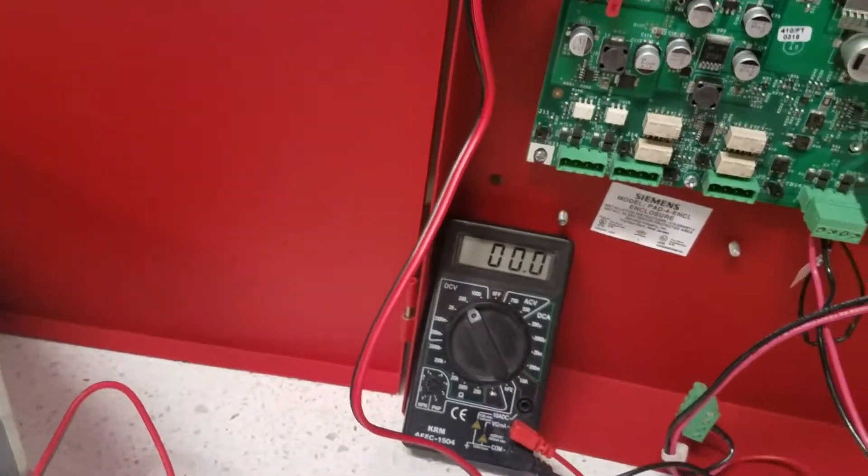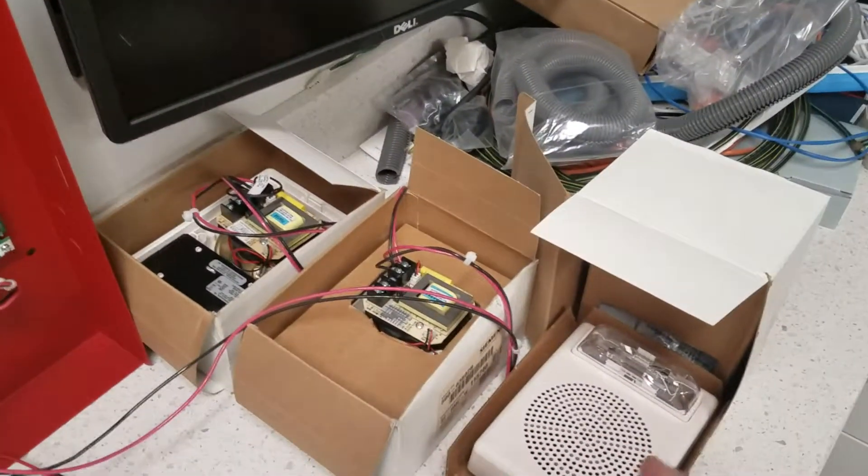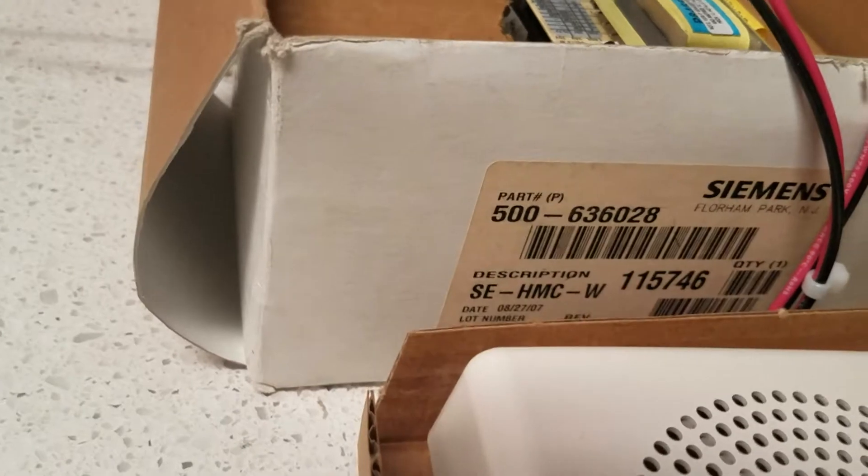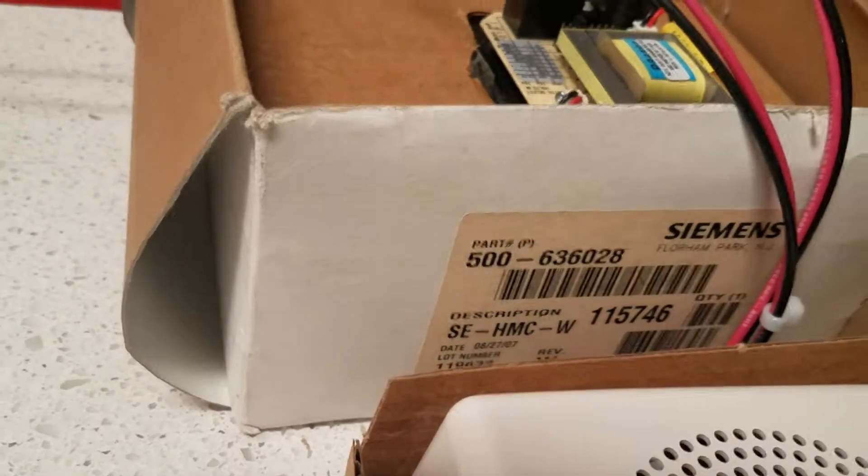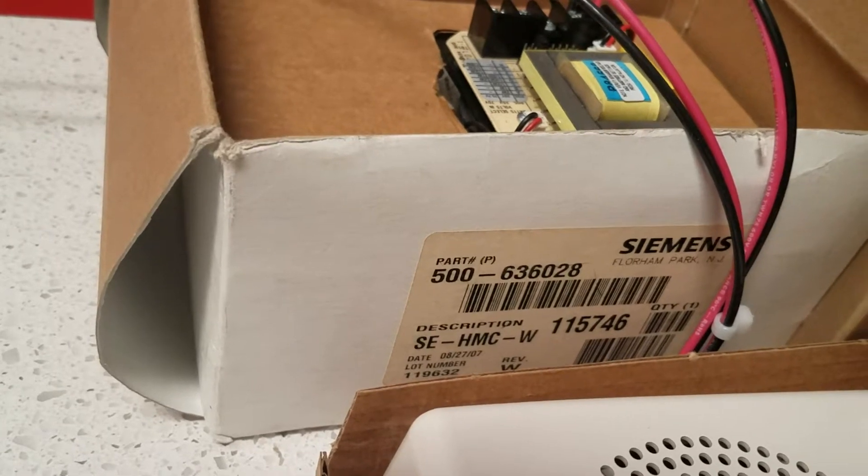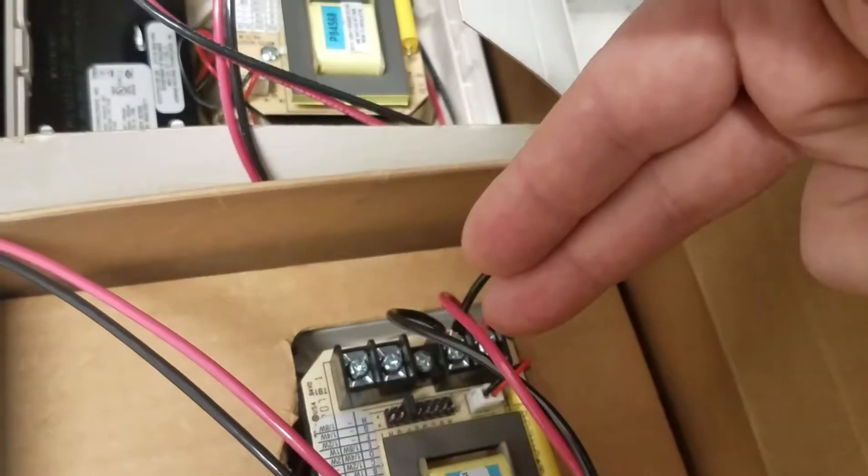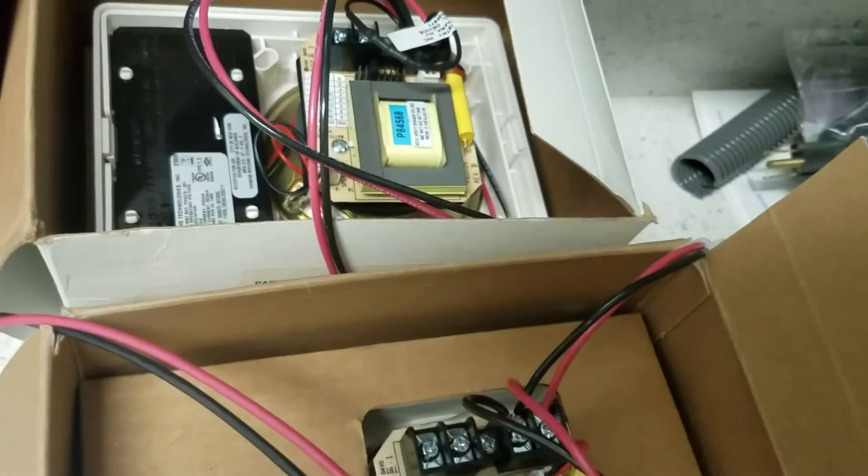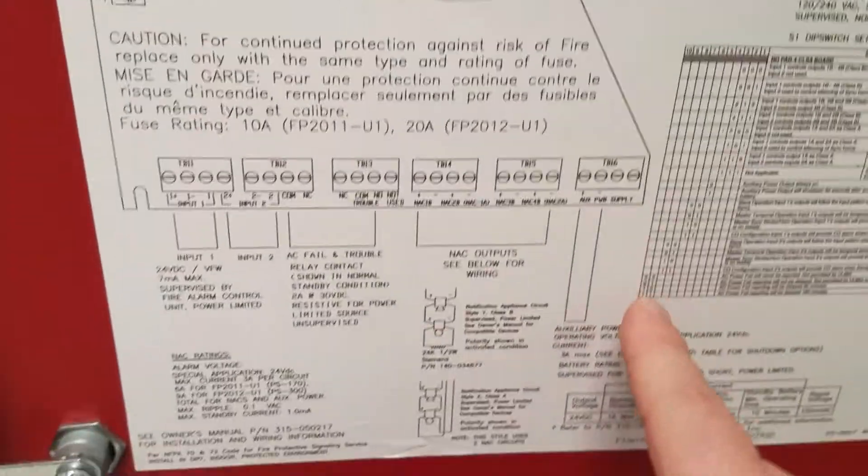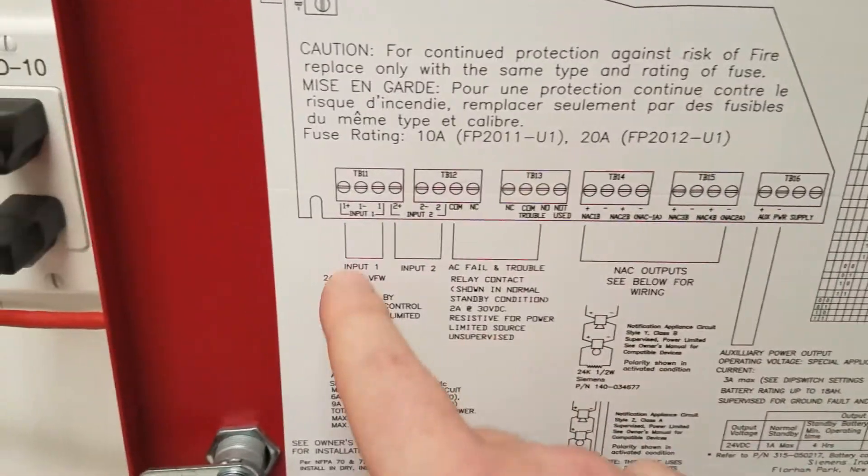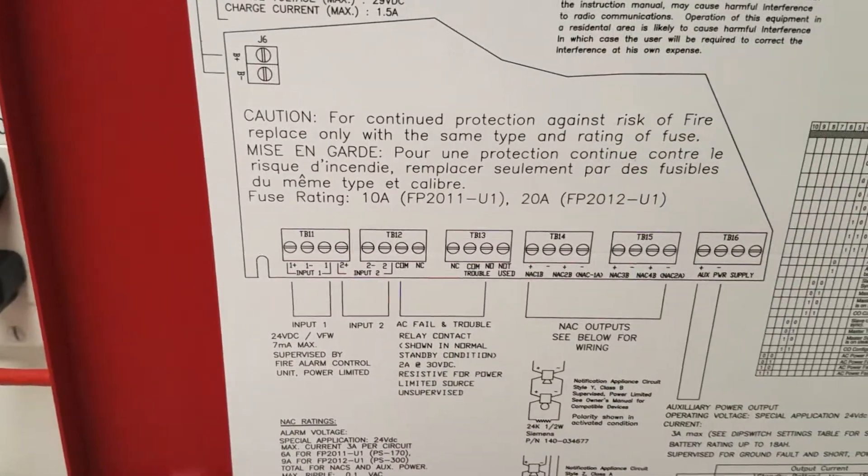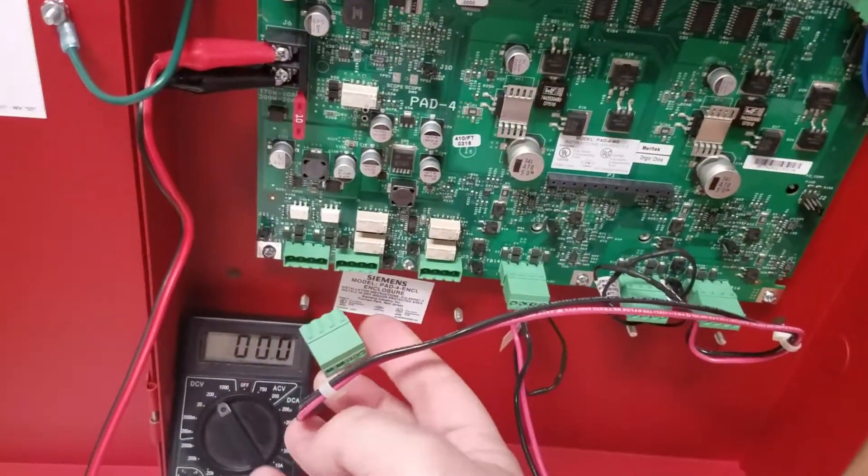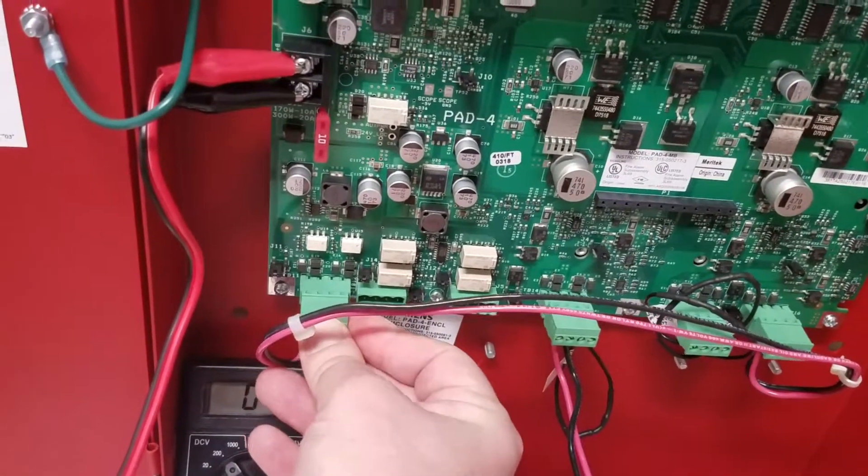So what I also have here is I have three speaker strobes, Model number SEHMCW. It is a speaker strobe, high multi candela, white. As you can see I am only connecting up the strobe circuit. I'm leaving the speaker circuit because I'm not testing the voice at this time. So to activate the strobes I am taking the power out from the aux power and I am putting it into the input one to activate the strobe circuit. That's what this jumper here is for. So let's go ahead and show you the activation of the strobes.